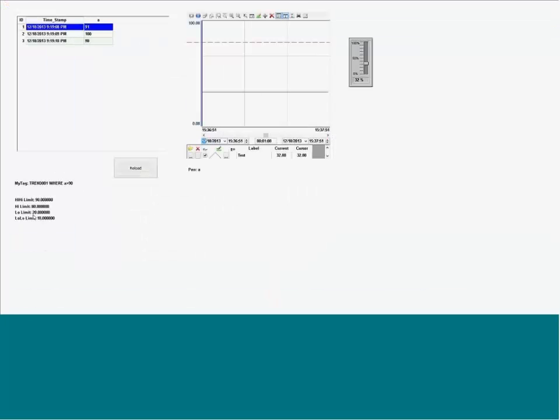And here you can see all the limits, and I can change them right here on the fly. So I can say the limit for high is no longer 80, it is 40, for example. And automatically I change the high limit for the tag. So it's that simple to view the limits for the alarm, to change the limits for the alarm, and to assign different limits to the same tag.